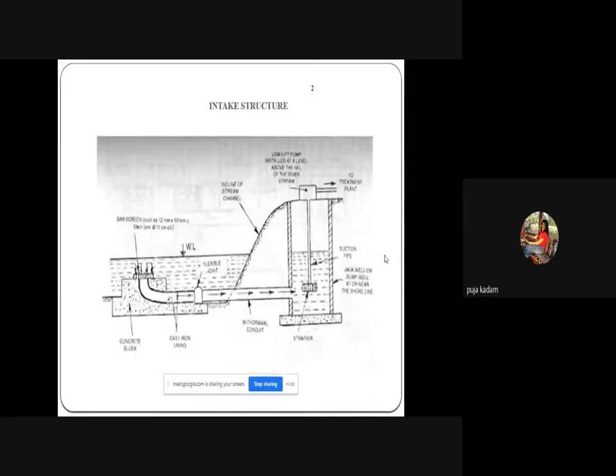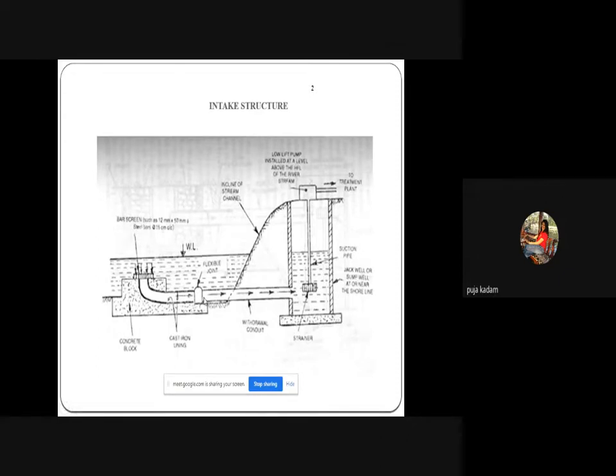A simple submerged intake structure is located on a river or stream side. You have a concrete block with a withdrawal conduit or pipeline, flexible joints to overcome temperature stresses and expansion/contraction of the pipeline. Bar screens are provided to obstruct large particles or debris from entering the pipe. After screening, water enters the conduit and passes through a jack well or sump well.